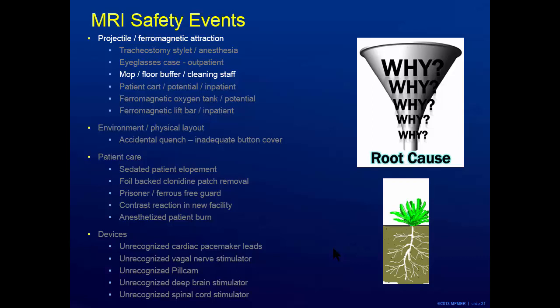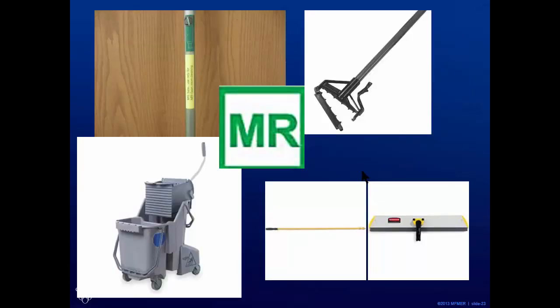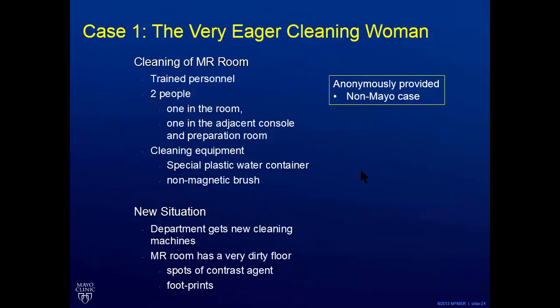No discussion of projectiles is complete without mops flying — and our shop is not unique in that respect. We had a mop fly into a magnet. After talking to the cleaning staff, we realized there was a ferromagnetic component in the mop, and he gave the classic line that he assumed he could control it. He found out he couldn't, particularly with the steep magnetic gradient field when you get close to a magnet. So we replaced all our cleaning supplies in our MR facilities with MR-safe items.